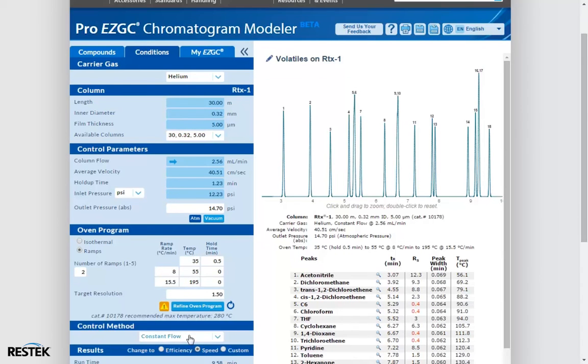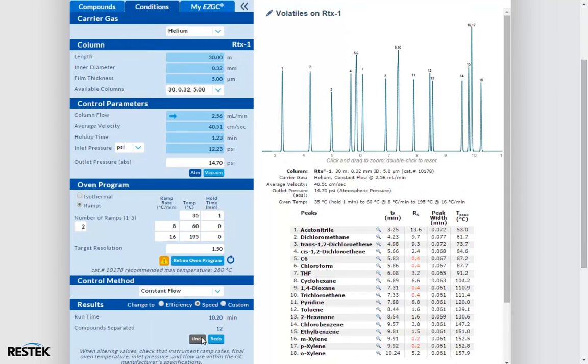We can see that the overall runtime has been increased by about 0.6 minutes. The software decreased the isothermal hold at the beginning of the run, reduced our intermediate temperature in the middle of the run, and reduced our ramp rate at the end of the run. If we want to go back to our original model, we can simply click Undo or use Ctrl-Z. The shortcut for Redo is Ctrl-Y.